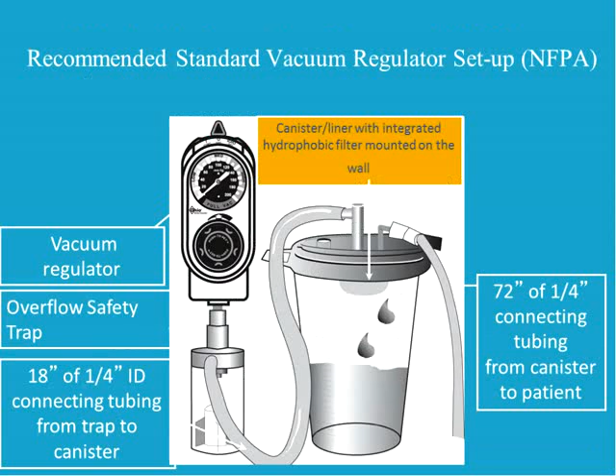So again, per NFPA recommendations, you should use a vacuum regulator, an overflow safety device, and then a filtered canister with the correct size and inside diameter tubing. So 18 inches of 1/4 inside diameter tubing from the canister to the vacuum regulator, and then no more than 72 inches of 1/4 inch connecting tubing from the canister to the patient.